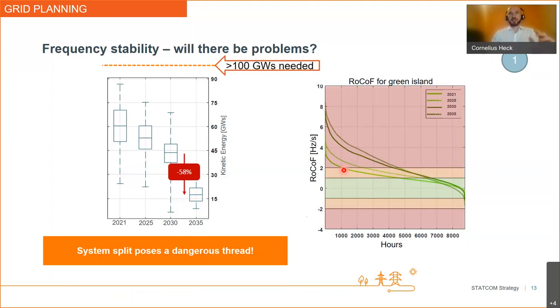And in order to counteract this, we would need to implement a lot of inertia in our grid. So for the 50 Hertz area, we would look at 100 gigawatt seconds that we would need. Or obviously, there is also a second option: we could just do massive amounts of redispatch in order to reduce the imbalance between the green and the blue island. But this of course will lead to massive costs, up to a few billions for each year.